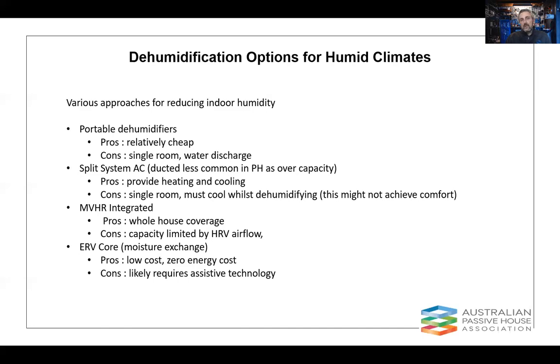They provide heating and cooling, so that's a good part of that option. The cons are in a split system format, they're really a single room and they must cool and dehumidify together. You can't separate those independently. We'll touch more on that. MVHR integrated, so what's possible there? The pros there are you get whole house coverage through your duct system, but you've got some limits again, like heating and cooling based on airflow. And ERV core, so moisture exchange. We'll sort of explain why that's going to need some assistive technology, meaning you're going to need some other form of dehumidification. It's just going to assist you.